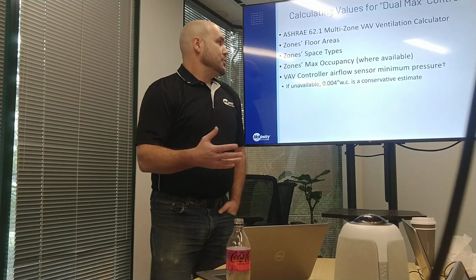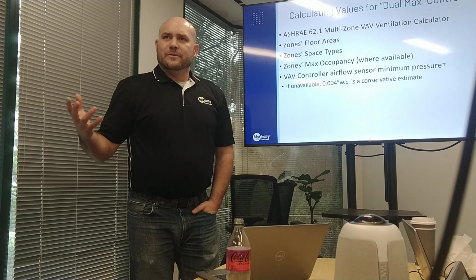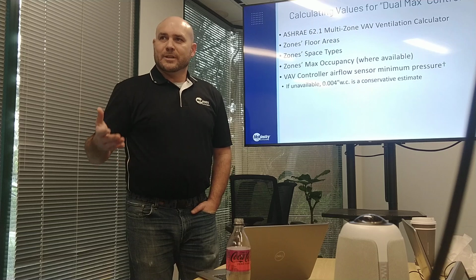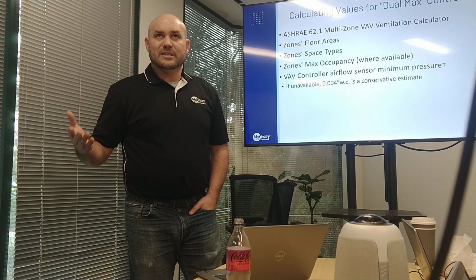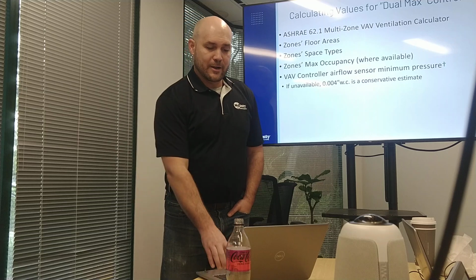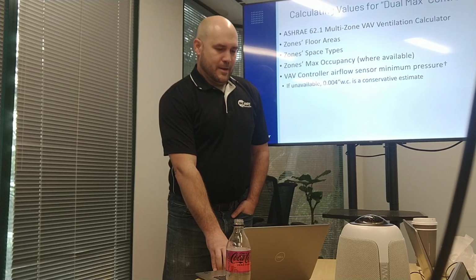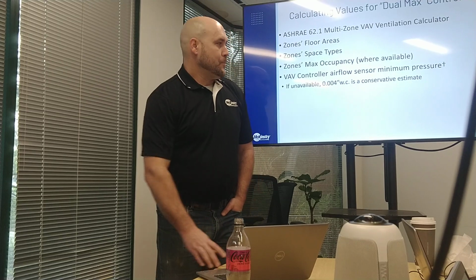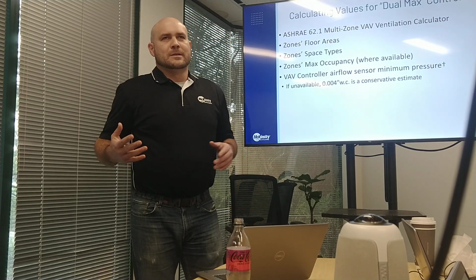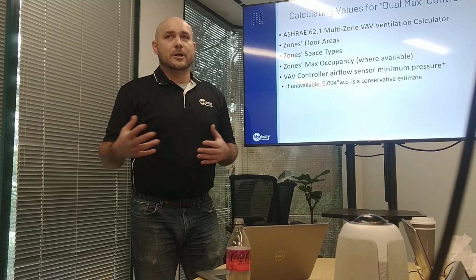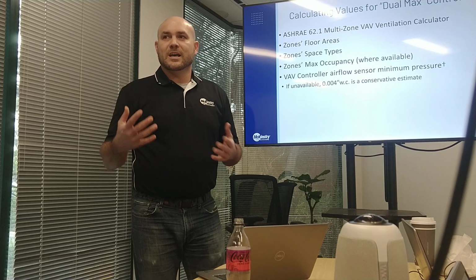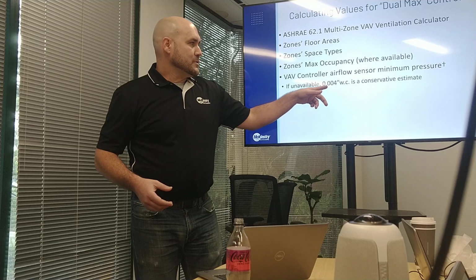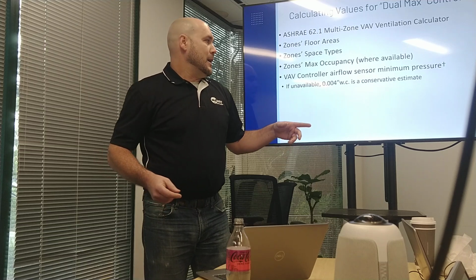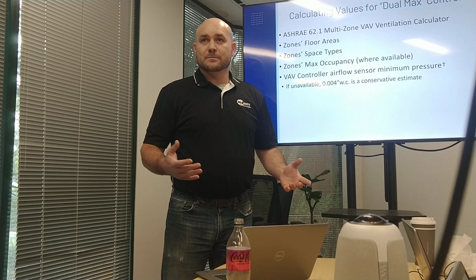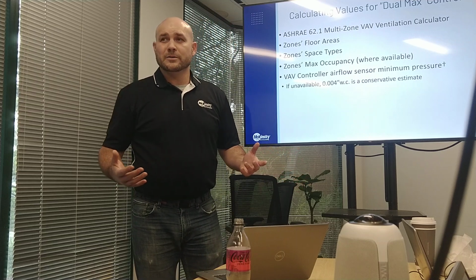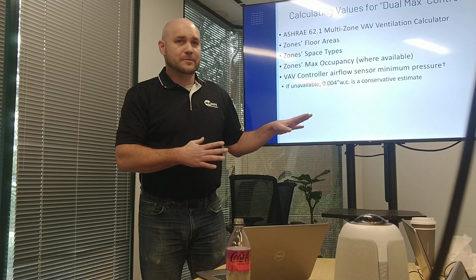The other input is how low the VAV controller can actually measure. That's going to be a limitation: how sensitive is the VAV box itself and how low can it control to. VAV boxes don't actually measure airflow, they measure velocity. And this 0.004 inches water column is a default. Most modern boxes can go down to 0.001, so this is quite a conservative estimate.